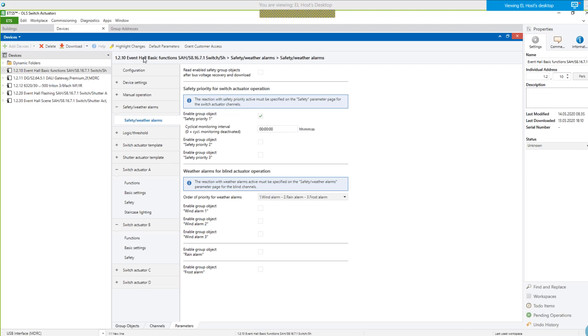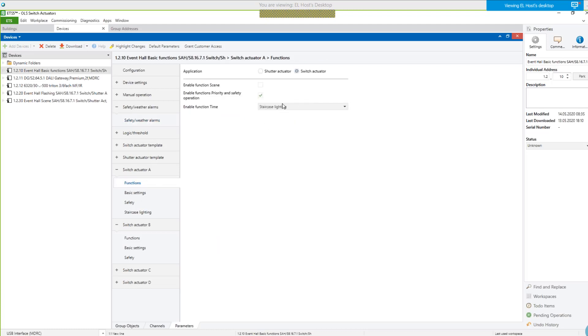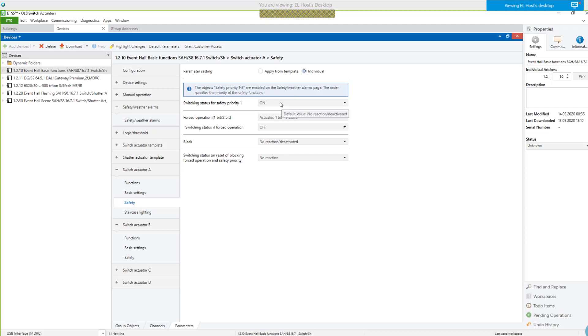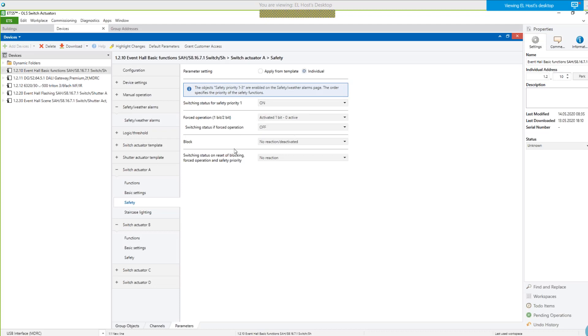These are the channel-independent parameters. Then I go to switch actuator A, where I have to program staircase lighting because it's the entrance area light. I also enable the safety functions, because I will use them for turning on the light due to fire alarm. Under safety, my safety priority one — fire alarm — results in an on command to turn on the light with highest priority. The forced operation function I use as well for switching off all lamps with an off command. The priority of safety priority one is higher than forced operation — that's the order. If priority two and three were enabled, they would be below forced operation.